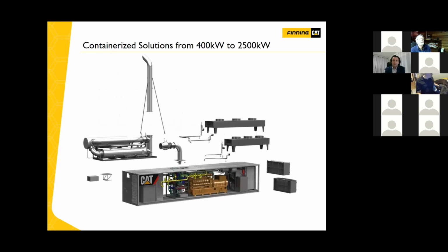On this particular unit from Finning and Caterpillar, we offer containerized solutions including all the equipment needed, similar to the site we've seen for the international airport. The equipment includes a generator set, heat exchangers on the coolant circuit, a heat exchanger on the exhaust, muffler and exhaust stack, emission after-treatment when needed, heat dump radiators, fresh oil tanks with oil makeup units, waste oil tanks, switchgear, and custom PLC controls. Finning Caterpillar is very well versed in providing custom PLC controls set up based on heat demand, electrical demand, and strictly to satisfy site needs.